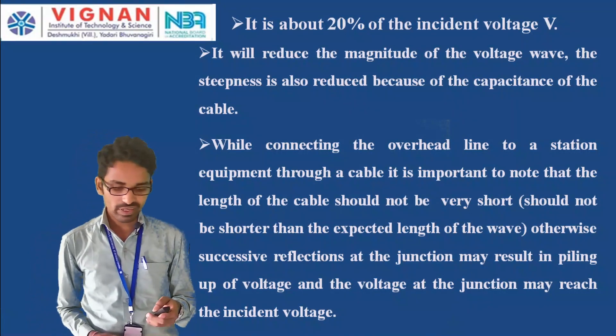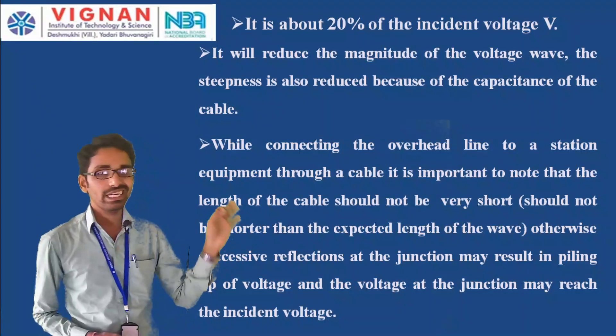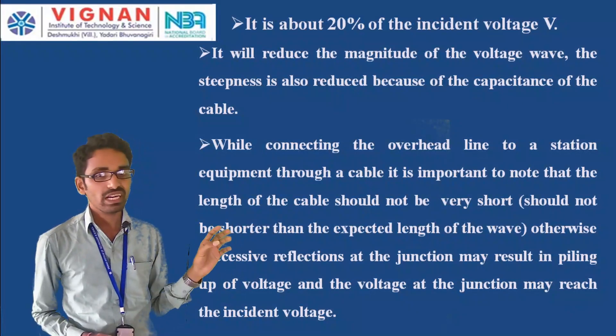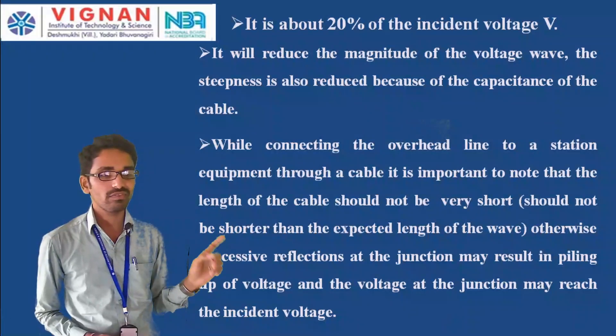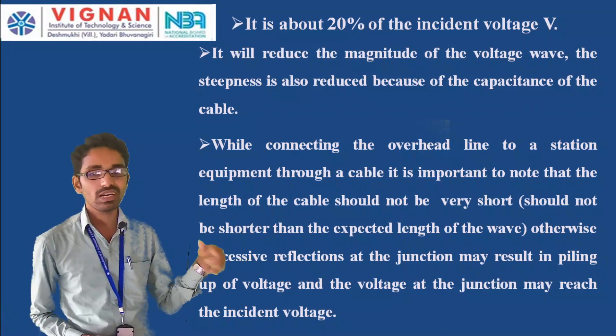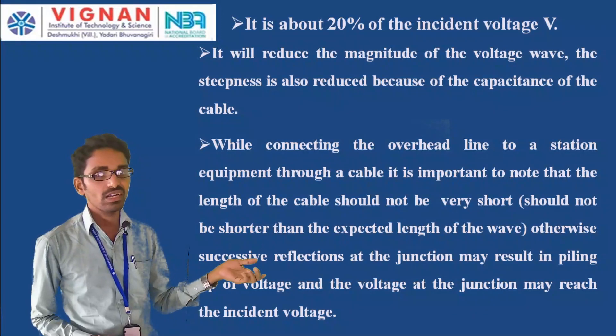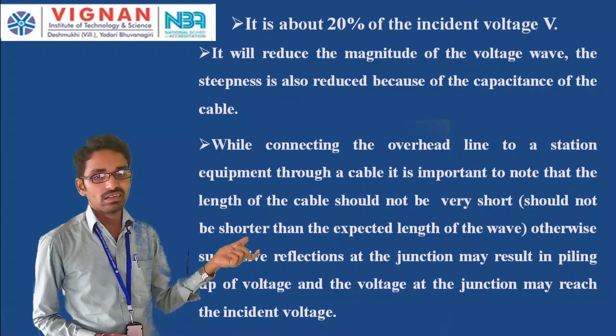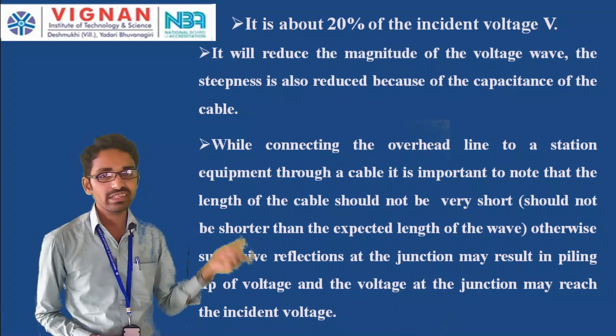While connecting an overhead line to station equipment through a cable, it is important that the length of the cable should not be very short — it should not be shorter than the expected length of the wave. If a very short cable is connected, successive reflections occur at the junction, which may result in piling up of voltage, and the voltage at the junction may reach the incident voltage level.